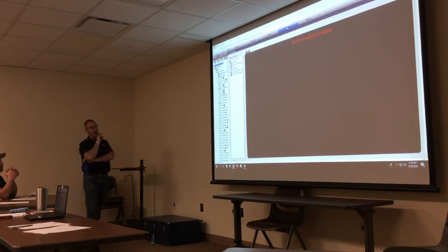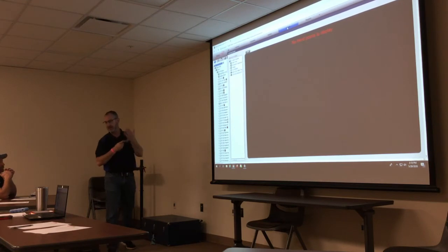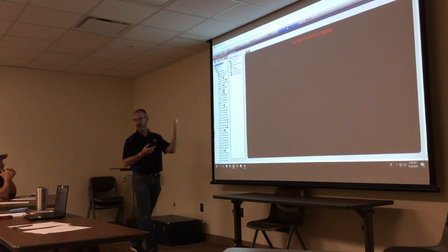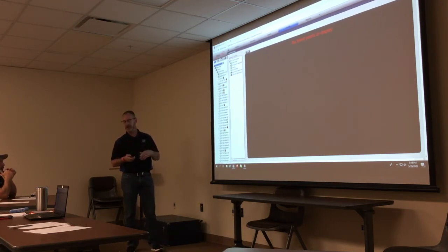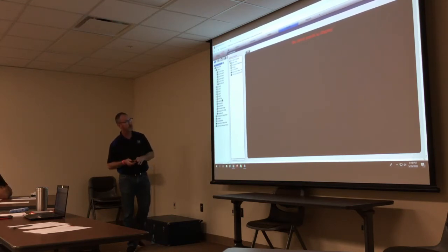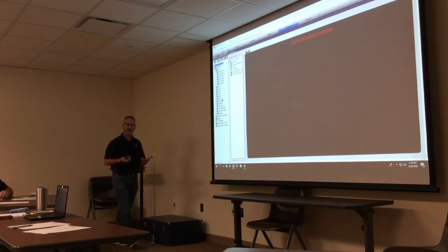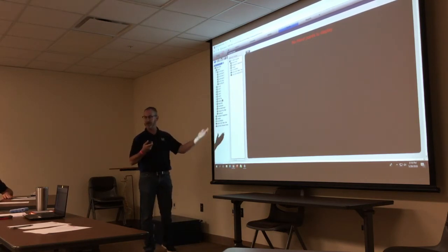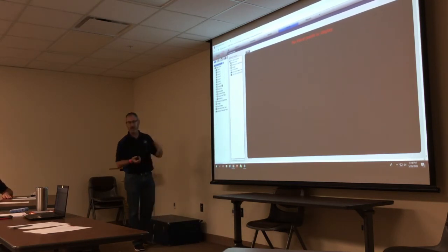All right, let's go up to trends. Trends are a graphical representation of points of data for you. So if it's a fan, you see the status on or off over a time window. If it's an outside air sensor or discharge air sensor, you can see the values of that sensor. You can also create your own trends to view, so if you want to look at the discharge air temperature of an air handler in relationship to the return temperature, you can put those two points on one trend.